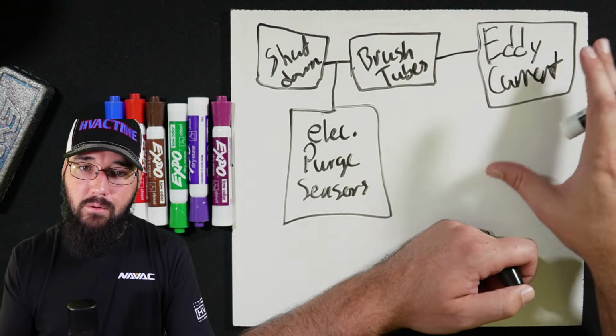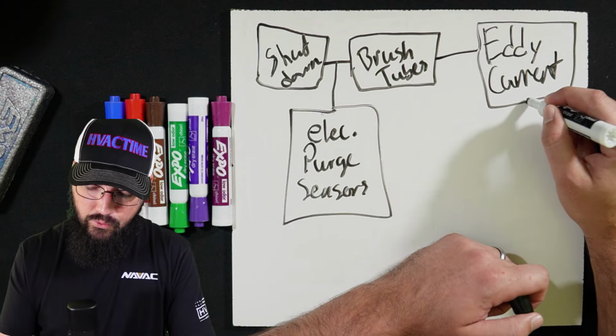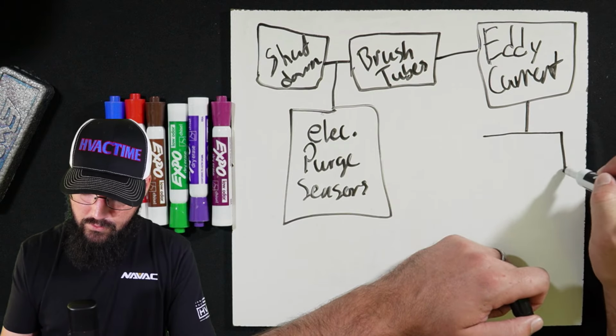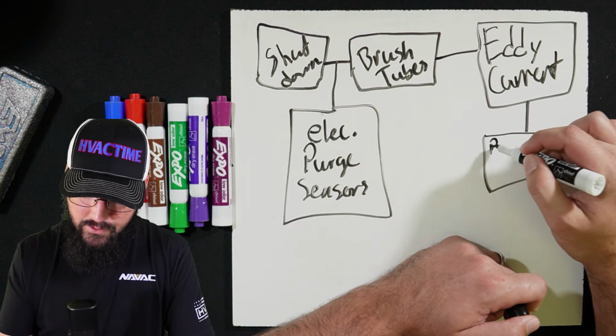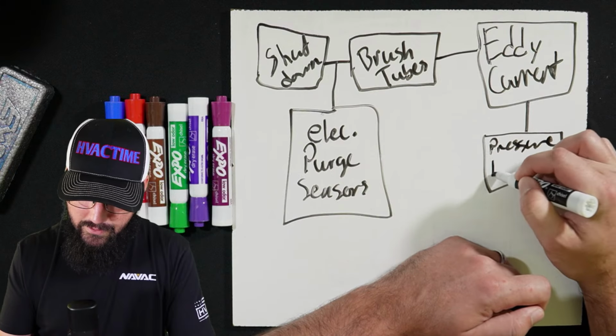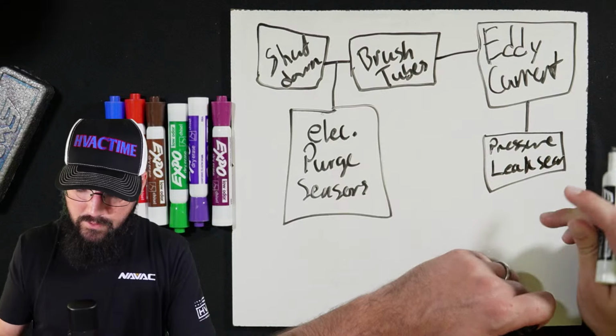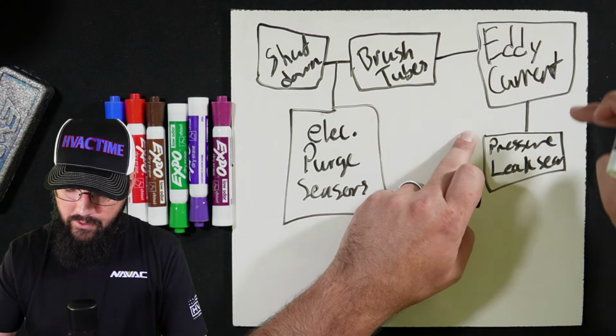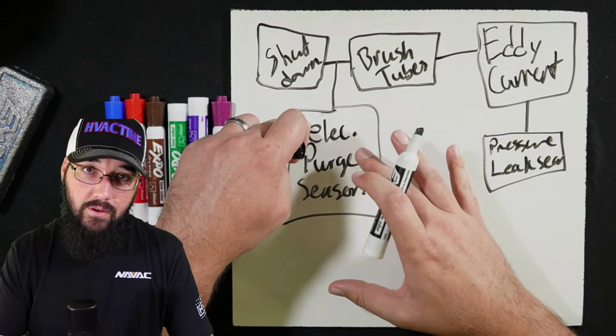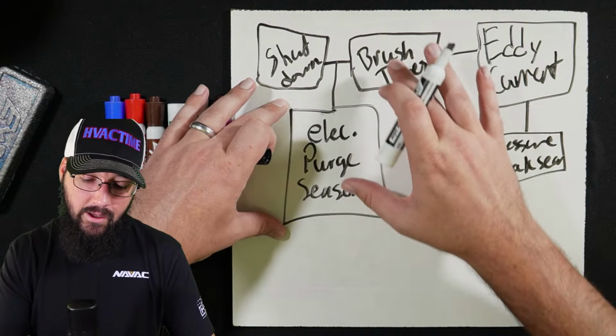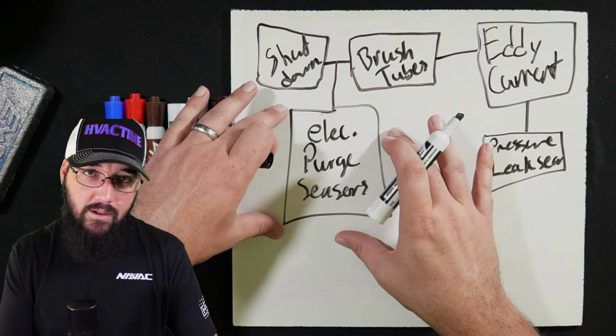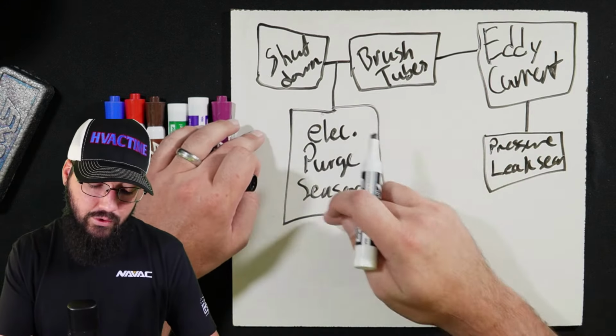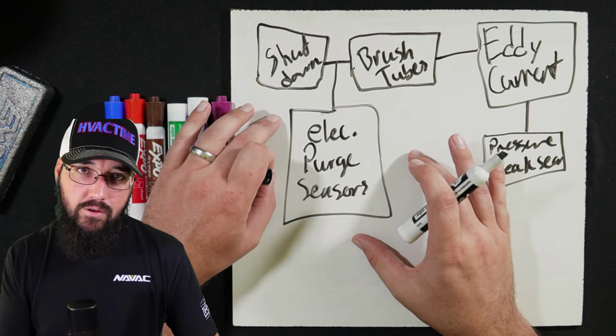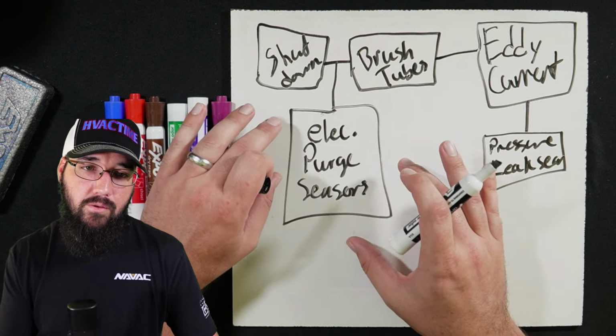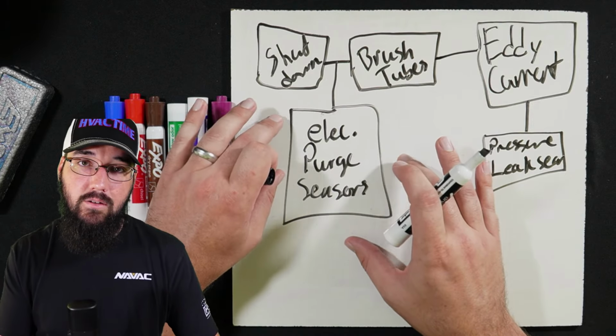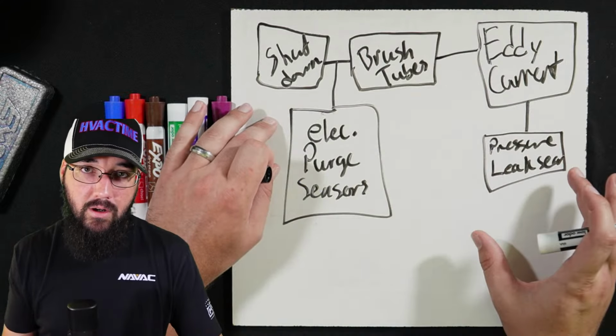When eddy current is done and we're wrapped up with that, then we can move into pressurization. So we want to pressurize and leak search. So: brush tubes, eddy current, pressurize and leak search. This guy who's focusing on all this has plenty of time to do it correctly, by the way. As all this is happening and he's helping support, he has plenty of time to go through this. That's one reason why this is where so many of our issues lie. So many of our issues. And so I am very meticulous with this process: take your time. Don't rush. And if we're doing a 2-man process, don't rush.